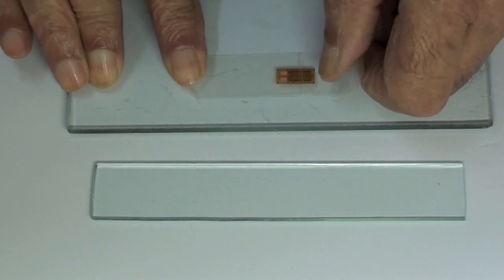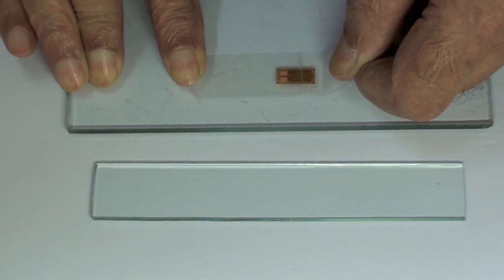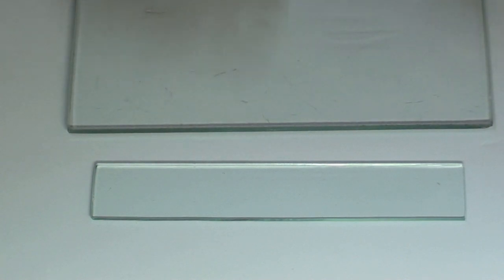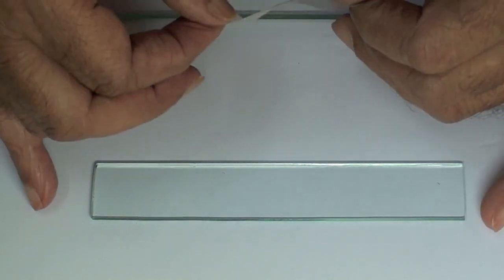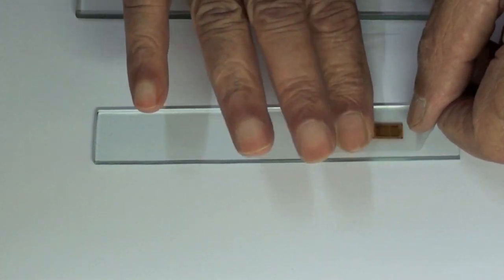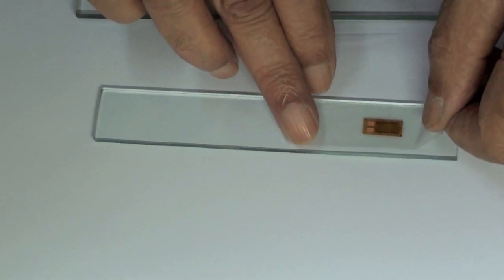The tape is lifted from the glass plate at a shallow angle to minimize the bending of the gauge. It is positioned on the surface of the part, then one end is pressed down on the surface and the rest of the tape is pushed down gently.